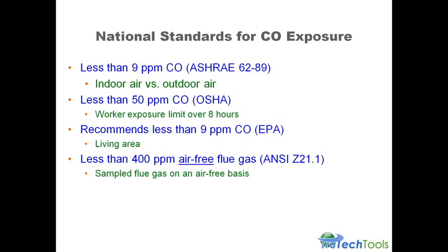The national standard for CO exposure is less than 9 parts per million. That's the ASHRAE 62-89 standard, and that's indoor versus outdoor air. If you live in New York City, you're going to have CO in your air outside. You walk outside, you're getting exposed to CO. Back in the day, they used to say you need to go to the country and get some fresh air. That's because your air is lousy in New York, and your body's getting poisoned by CO, which is a cumulative poison. You've got this stuff building up in your blood. You get away, get some fresh air, and you will feel better.